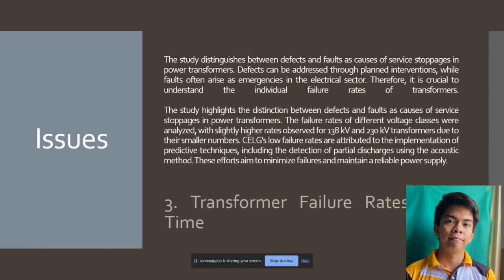Number 3. Transformer failure rates over time. The studies distinguish between defects and faults as causes of service stoppage in power transformers. Defects can be addressed through planned interventions, while faults often arise as emergencies in the electrical sector. Therefore, it is crucial to understand the individual failure rates of transformers. The failure rates of different voltage classes were analyzed, with slightly higher rates observed for 138 kV and 230 kV transformers due to their smaller numbers.